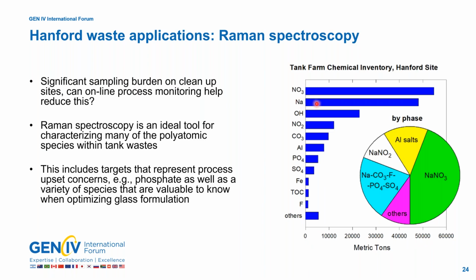If you sum up the major constituents - sodium salts of nitrate, hydroxide, nitrite, carbonate, aluminate, phosphate, and sulfate - those 6 or 7 constituents add up to over 95% of all the solid components in all the tank waste out in the Hanford area. Excluding water, 95% of what's in the tanks are Raman-active sodium salts, which is why we use Raman spectroscopy - you can measure 95% of the constituents in one spectrum.